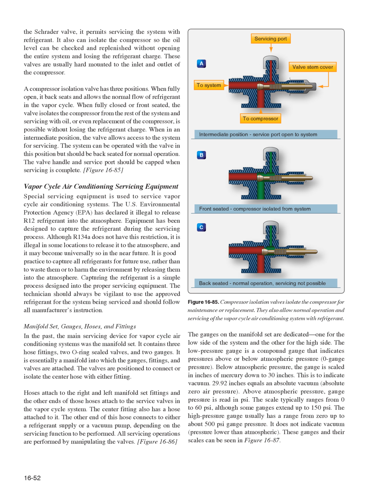A compressor isolation valve has three positions. When fully open, it back seats and allows the normal flow of refrigerant in the vapor cycle. When fully closed or front seated, the valve isolates the compressor from the rest of the system, and servicing with oil, or even replacement of the compressor, is possible without losing the refrigerant charge. When in an intermediate position, the valve allows access to the system for servicing. The system can be operated with the valve in this position but should be back seated for normal operation. The valve handle and service port should be capped when servicing is complete.